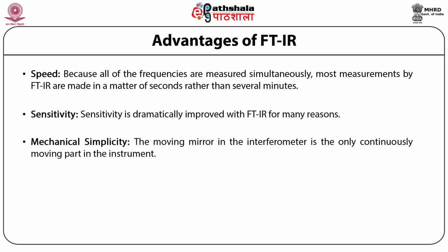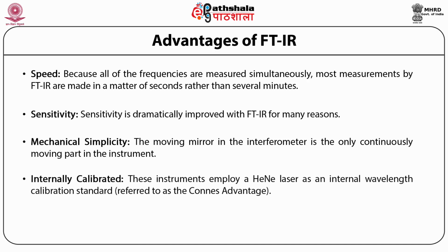Mechanical simplicity: the moving mirror in the interferometer is the only continuously moving part in the instrument. Thus, there is very little possibility of mechanical breakdown. Internally calibrated: these instruments employ a helium neon laser as an internal wavelength calibration standard. These instruments are self-calibrating and never need to be calibrated by the user.